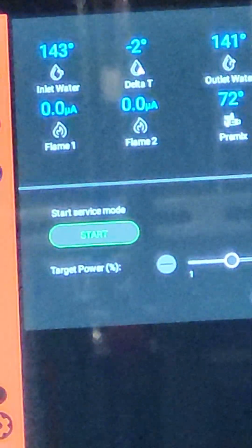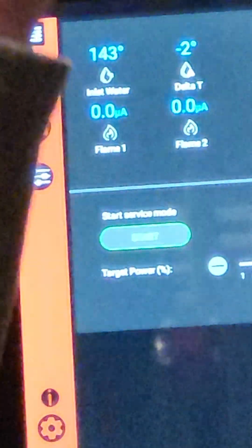Service maintenance screen. My bad, fingers, that's the wrong one. Service maintenance screen would be what you use if you're going to do combustion each year. I don't know if you guys do combustion on your units or have an outside contractor do it, but service mode is a manual way to make the boiler fire. We would press start, the boiler would start running, it'd start moving the pump, and then we could select full fire 100% or minimum fire, and then we could move the dial and go anywhere we want, every specific firing rate, if we wanted to adjust it.